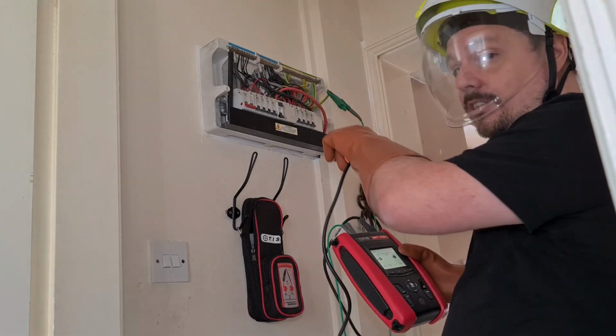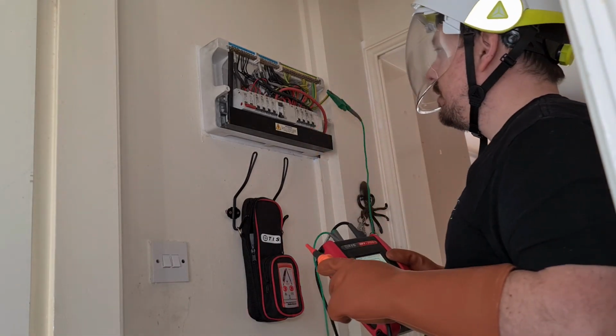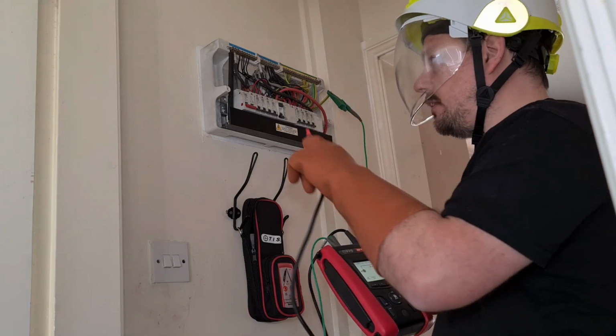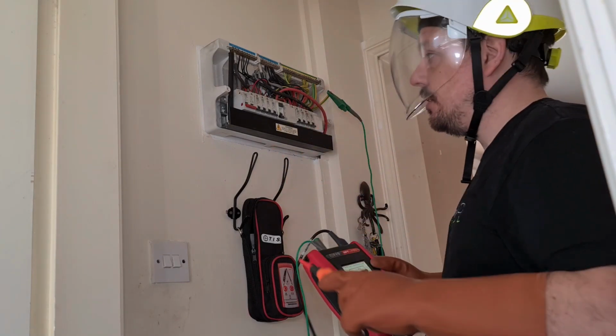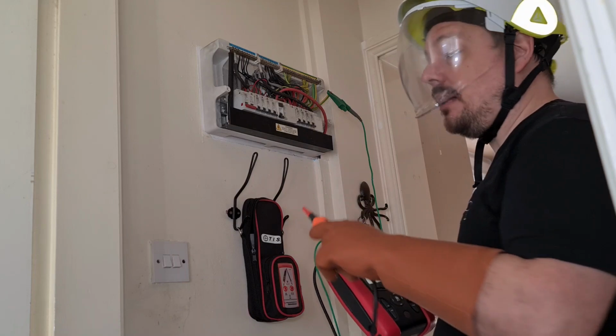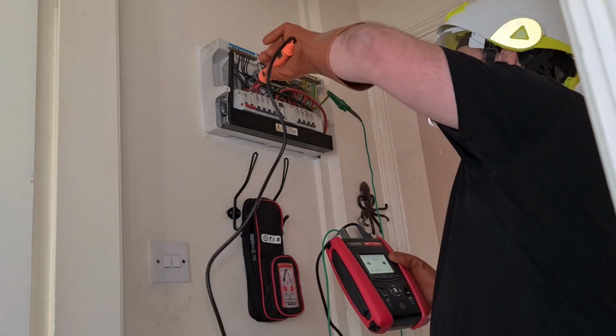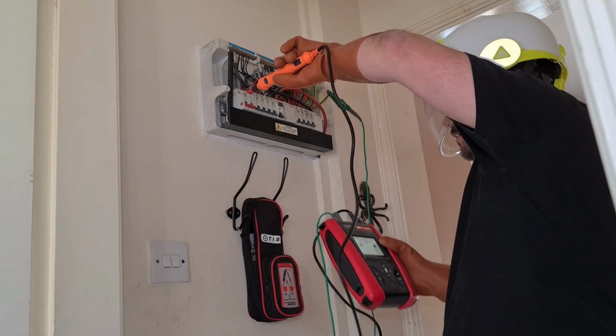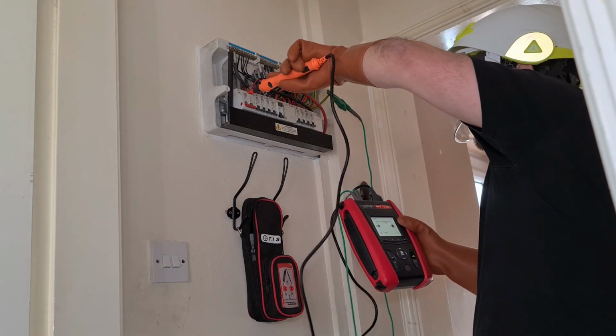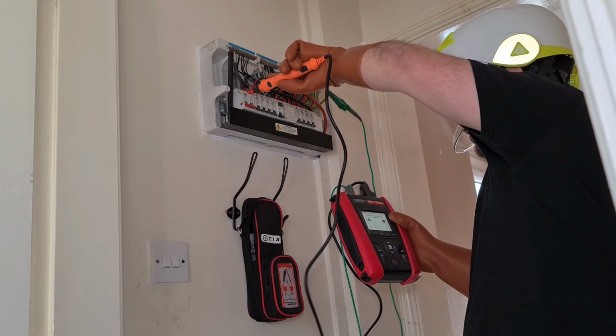Essentially you've got your earth disconnected - we don't want any of the parallel paths in place while we take this measurement. I'm now going to probe onto the incoming line and see what value we get. So if I pop my probe on, the test set should start to measure voltage, which it is doing.